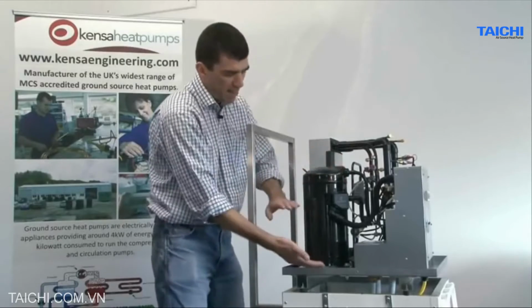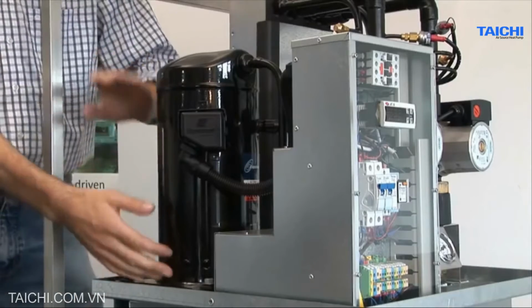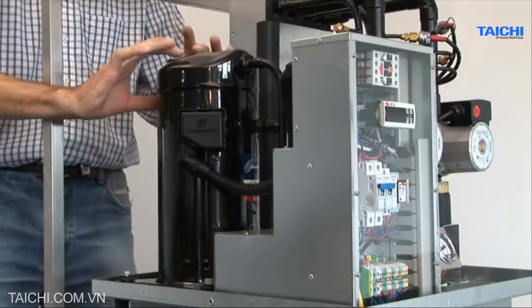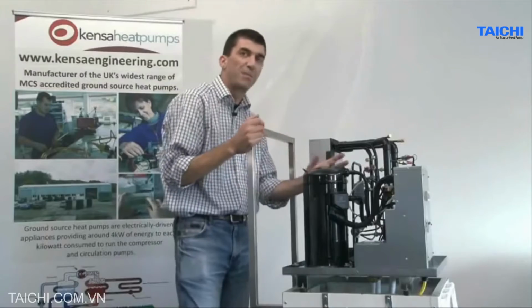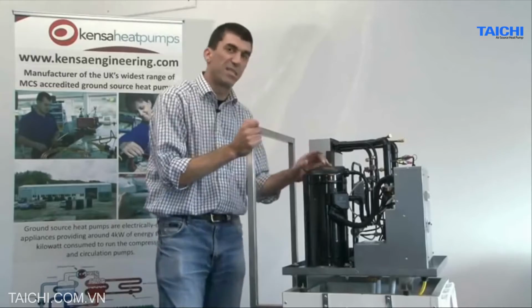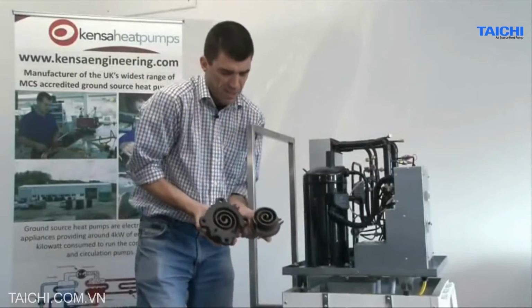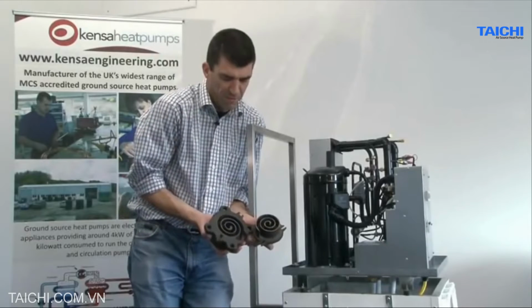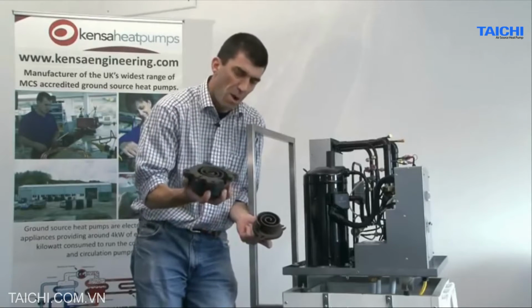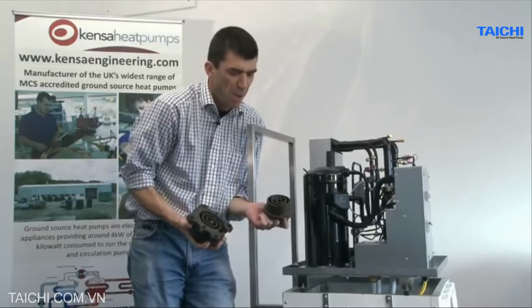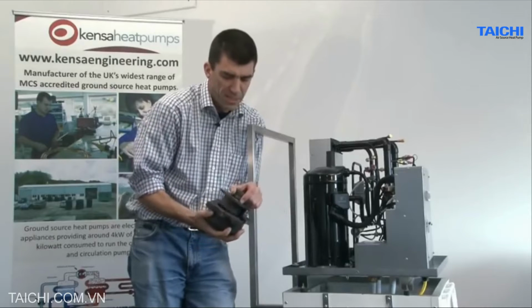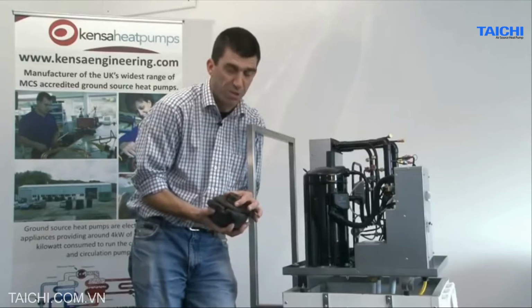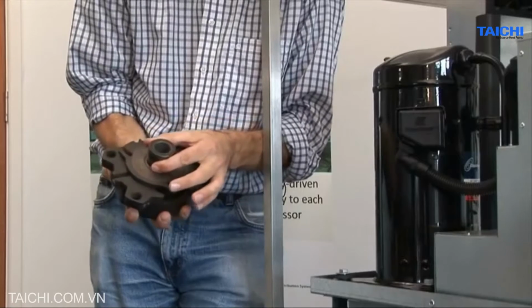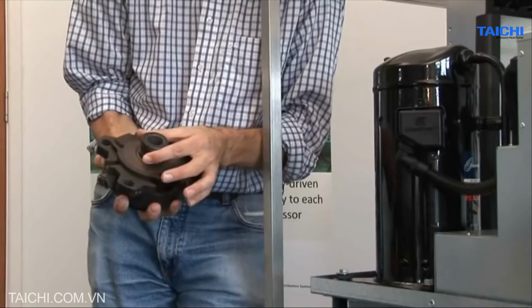Actually inside here, there's mostly electric motor, but in the top half is the scroll set. That's the pump, the gas pump that moves the gas around the system. I'm going to come back to the gas, but in terms of the working parts, this is the working components of a scroll set. This part in my right hand is fixed. The part in my left hand orbits, driven by the electric motor. It moves in a simple round and round mechanism.